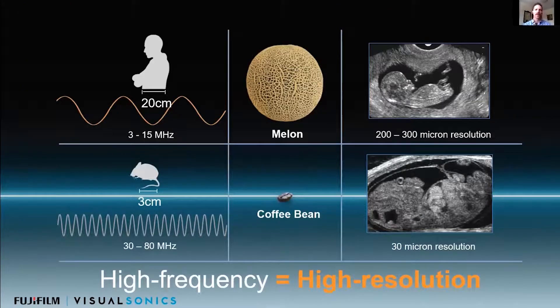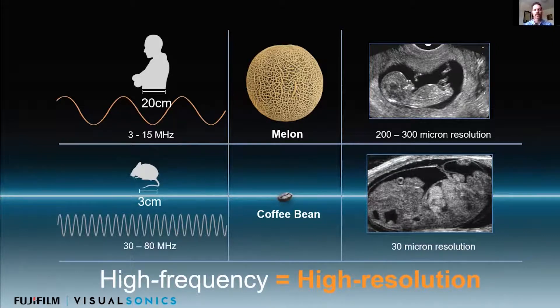Typical ultrasound operates in the 3 to 15 megahertz frequency range. We are operating in the 30 to 80 megahertz frequency range. The two images on the right show one is a human fetus and the other is a mouse fetus. We're going right down to about 30 micron resolution with our highest frequency transducers.